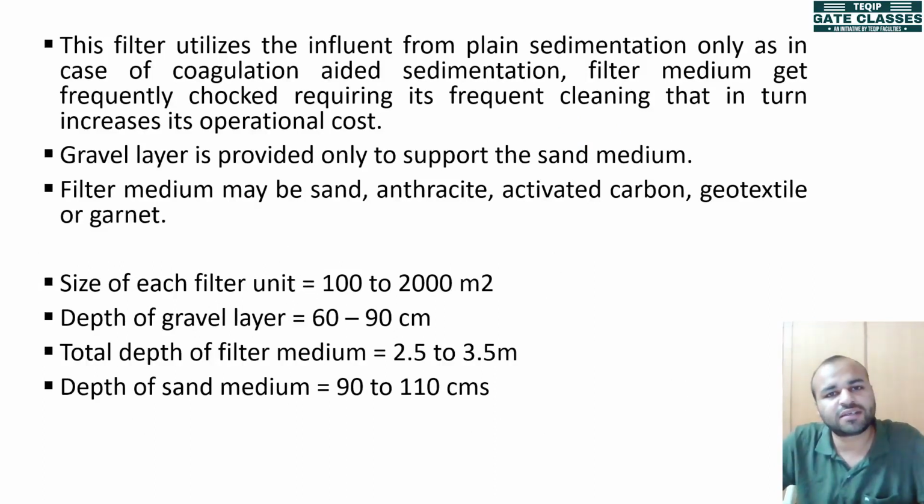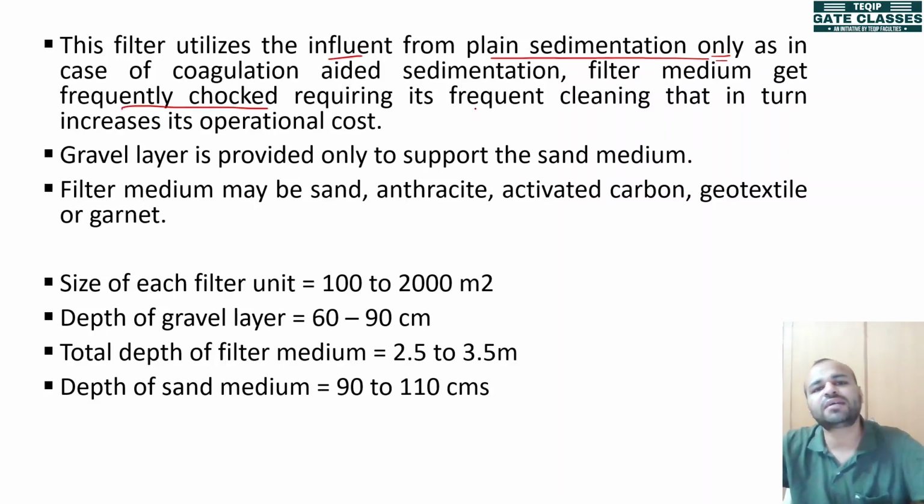So this filter utilizes the influent from the plain sedimentation process. Okay, I have written here only because we don't use the coagulation aided sedimentation, because it will eventually choke the filter bed a little more. As it is also written here, in case of coagulation aided sedimentation, the filter medium gets frequently choked, which requires its frequent cleaning, that increases its operational cost.